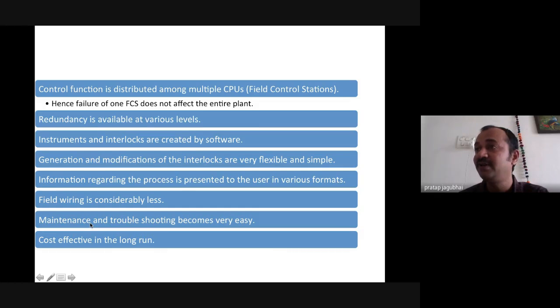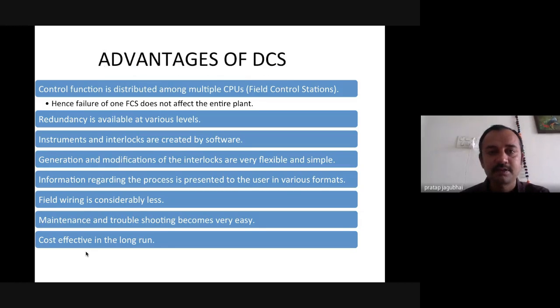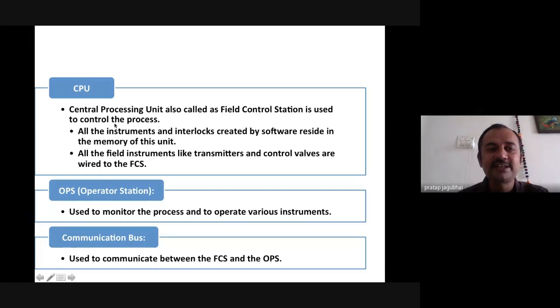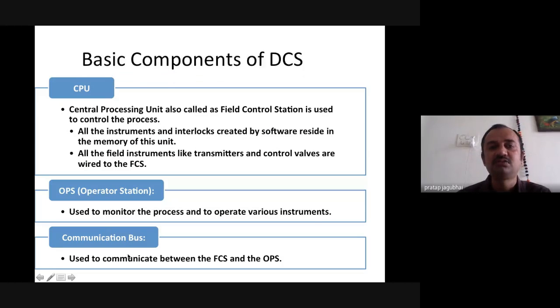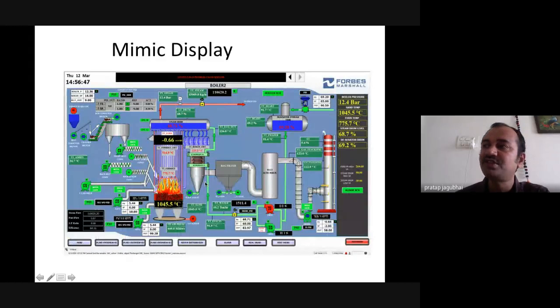Also, redundancy can be available, where you can have two computers, two CPUs, and the IOs can be redundant. So if one channel fails, the second channel automatically overrides the control. Again, as I said, the representations of the SCADA, the machine interface and the screens are so easily understood that you can very easily configure and control the parameter. So this is the typical construction of the DCS system, comprising CPUs, IOs, operating stations, and the communication bus. Now, how does the centralized control system look?